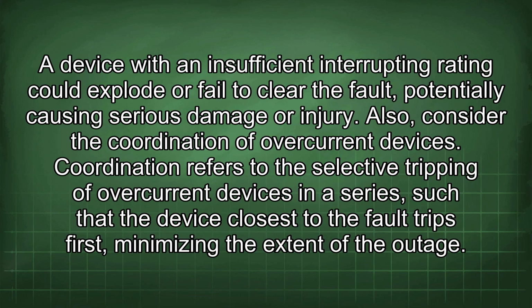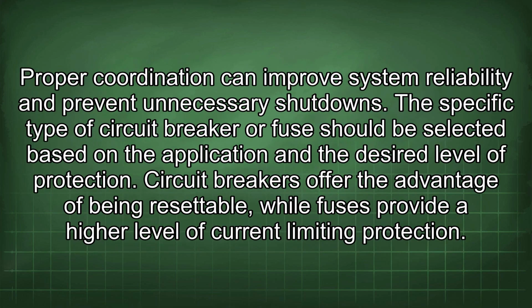A device with an insufficient interrupting rating could explode or fail to clear the fault, potentially causing serious damage or injury. Also, consider the coordination of overcurrent devices. Coordination refers to the selective tripping of overcurrent devices in a series, such that the device closest to the fault trips first, minimizing the extent of the outage. Proper coordination can improve system reliability and prevent unnecessary shutdowns.